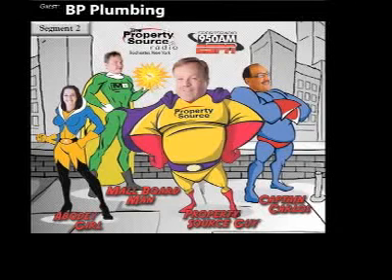And I may look into the idea of a tankless water heater. Does it matter how old or how new the house is? Because my house is really old. It doesn't matter. You start the process from scratch. We run a new gas line right from the meter to the tankless, because the traditional water heater is 40,000 BTUs. The smaller model tankless is 180,000 BTUs.